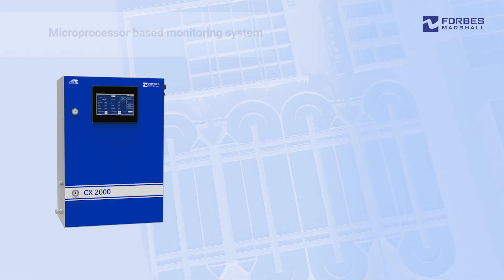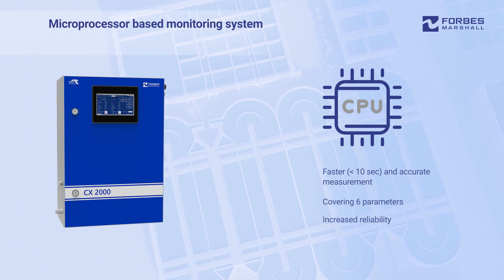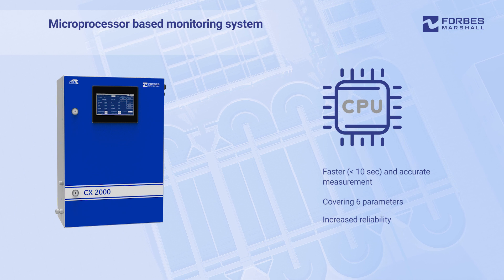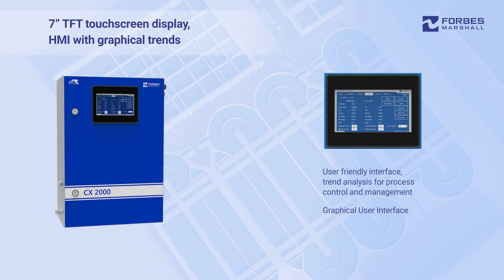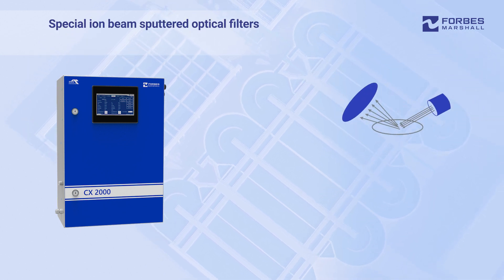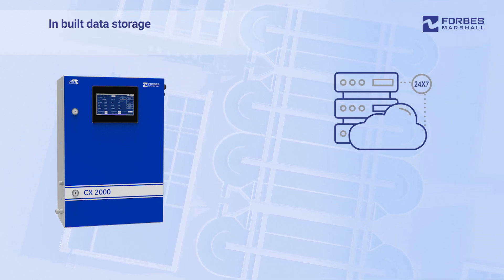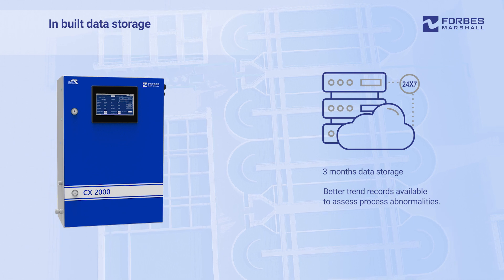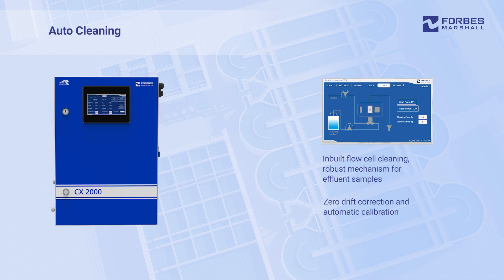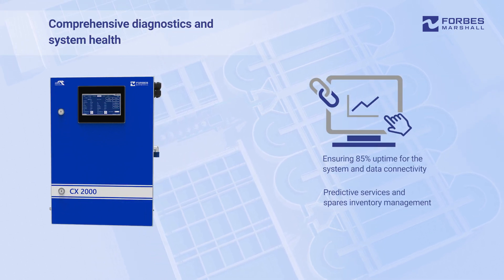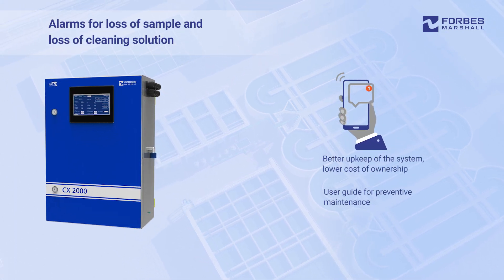The CX2000 comes equipped with a state-of-the-art advanced ARM Cortex M4 core 168 MHz CPU, a 7-inch TFT touchscreen display, HMI with graphical trends, special ion-beam sputtered optical filters, in-built data storage, auto-cleaning and auto-zero calibration system, comprehensive diagnostics and system health, and alarms for loss of sample and loss of cleaning solution.